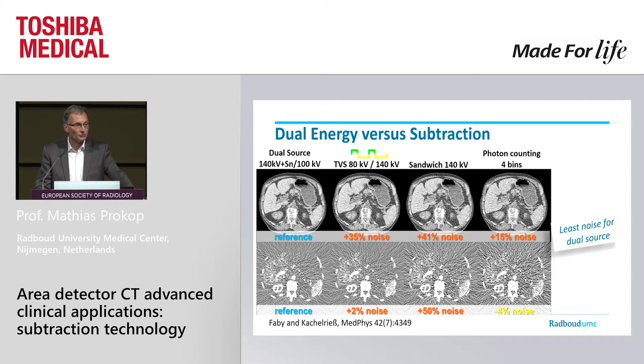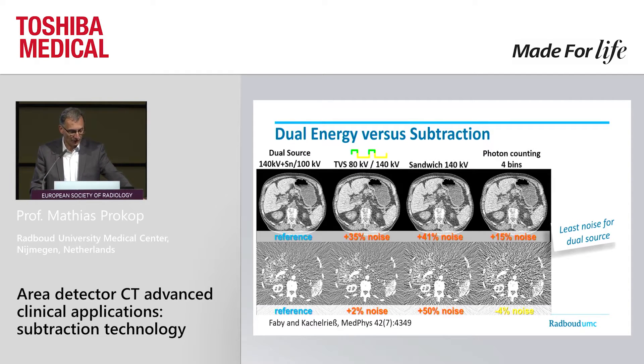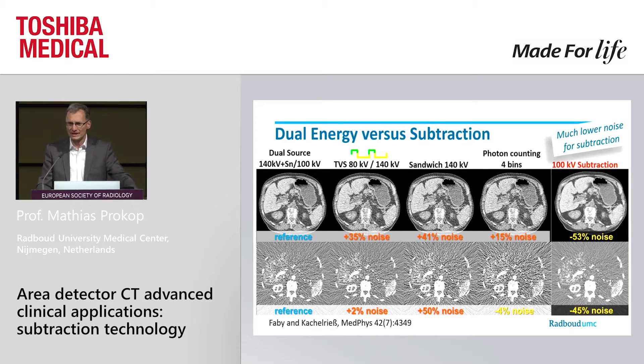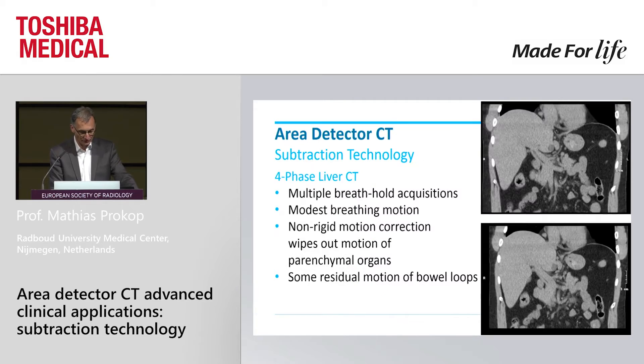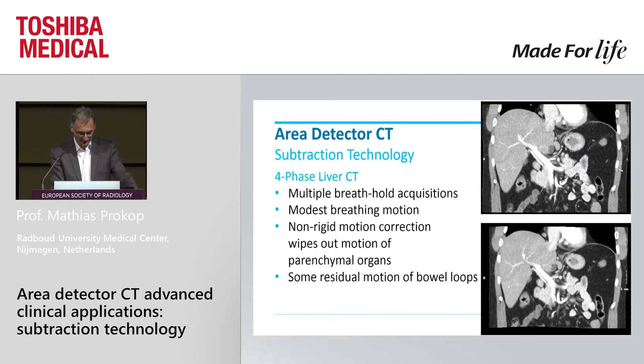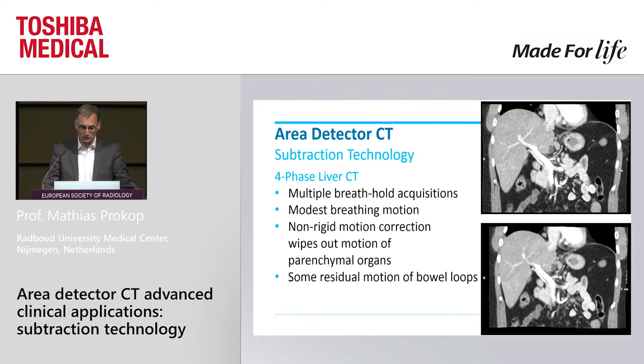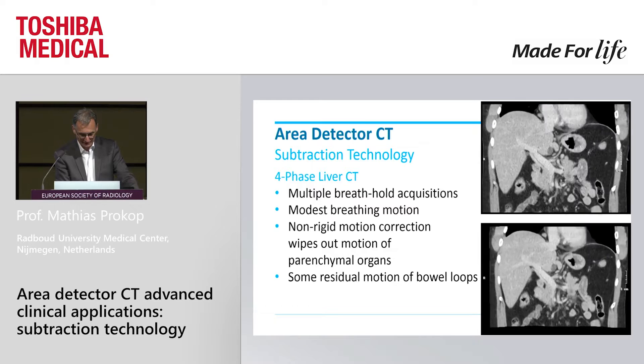A simulation done by someone closely linked to Siemens evaluated the various dual energy applications — dual-source imaging, rapid kV switching, sandwich detector, and even photon counting. It turns out that photon counting is a little bit better than dual-source for iodine images, but dual-source actually does extremely well in everything else. Comparing that to subtraction, there is a substantial difference: we have 50% less noise on the pre-contrast and the subtracted image — superior technology when it comes to signal-to-noise ratios. The problem is you need registration. We can register multiple breath-holds, which wipes out motion of parenchymal organs, but in areas with bowel motion there is some residual motion.